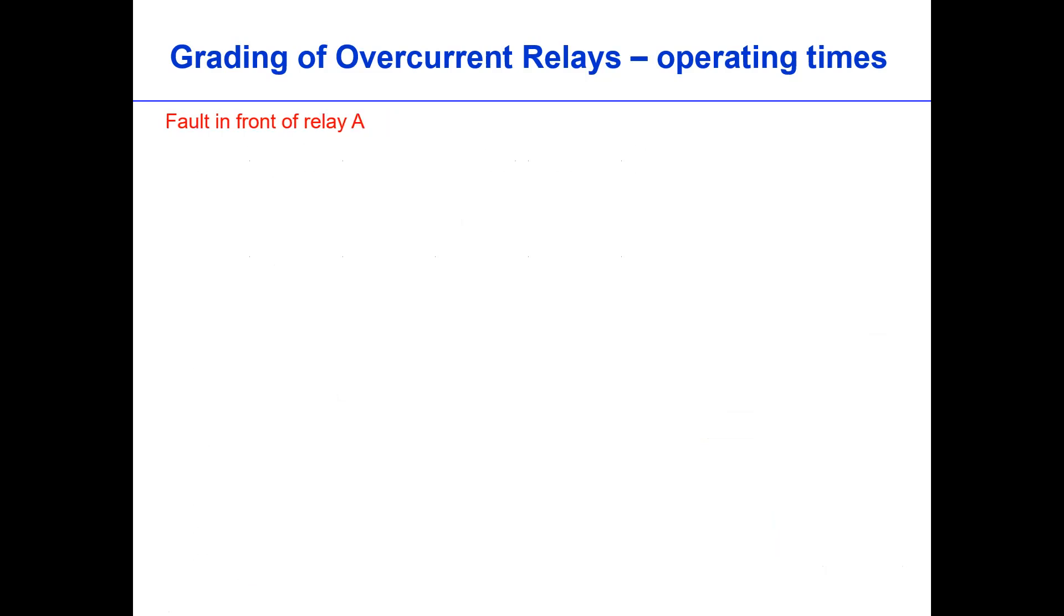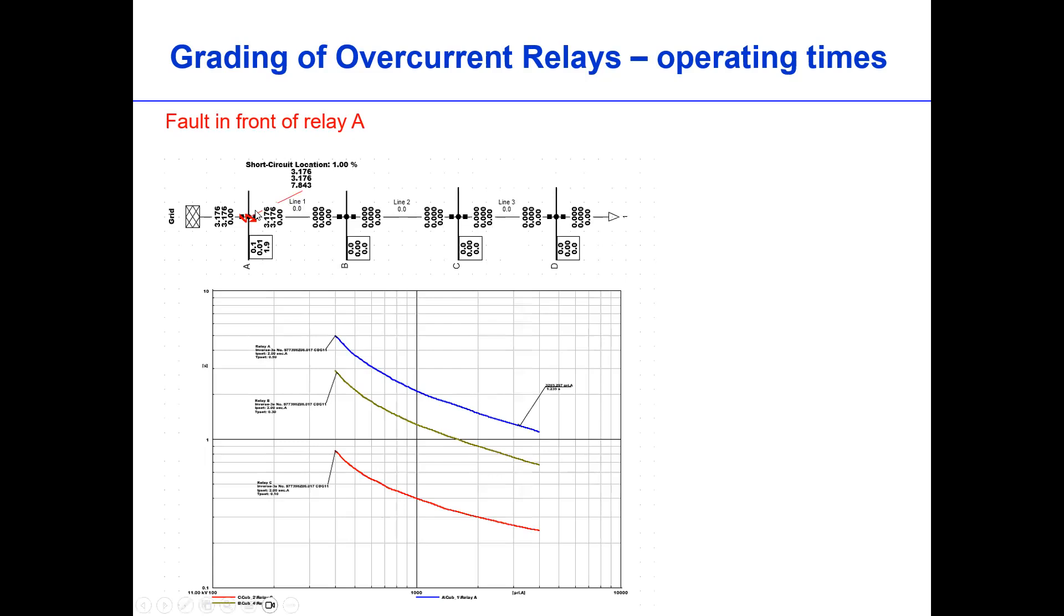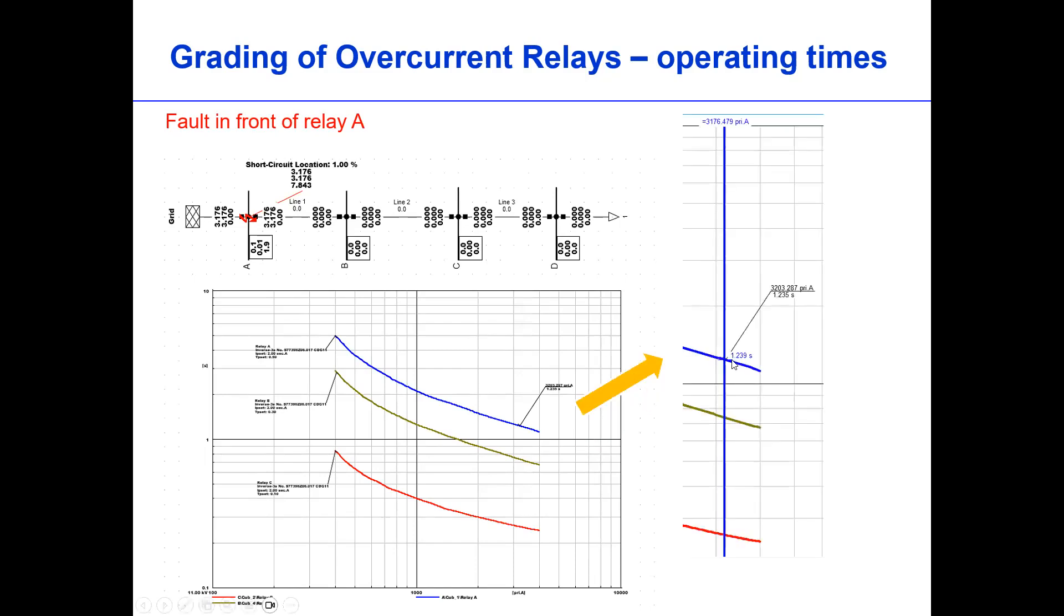So what about for relay A? Well, in this case, the fault is just near the generator. Only the relay near the fault trips, which is relay A, at 1.23 second. Relay C and B are not tripped. That is the only disadvantage of overcurrent relay grading. For the last fault magnitude, the trip time is longer. It takes 1.2 seconds, and there is no backup for this one.